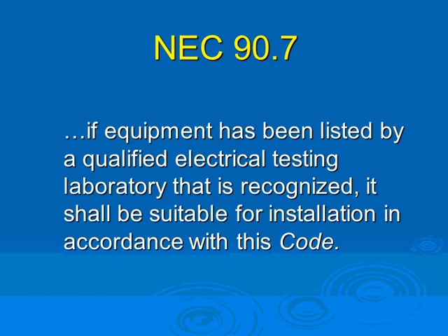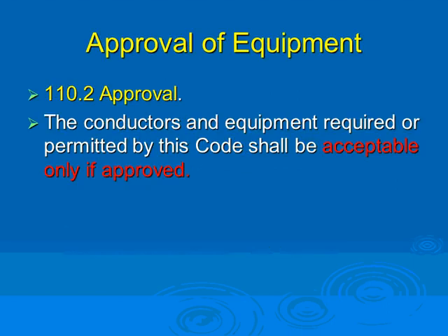Yes, sir. Very quickly, if you had a situation like that in a hospital, so the hospital bought something from some other country, Australia, and they brought it in and actually built it on site, and the inspector came in and said all these pieces with this device are not listed, you need to do something else here. And so that was applicable. They had inspectors come out, and an engineer proved it. Right. So the state had to come and say it. Absolutely. So that's the alternative, and it's closer than you think, guys, because we buy equipment from all over the world, and most of the manufacturers are aware of UL listing and they list them. Some are not. So we have to get into finding an engineer or a third party to approve it.